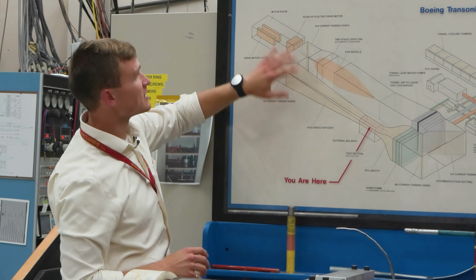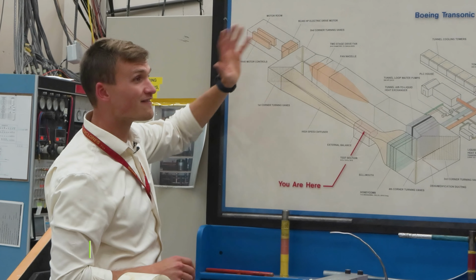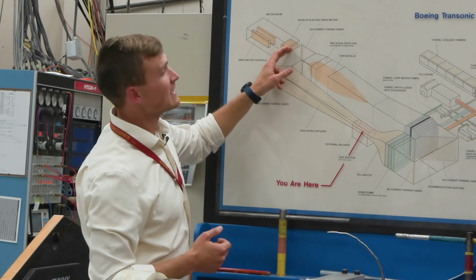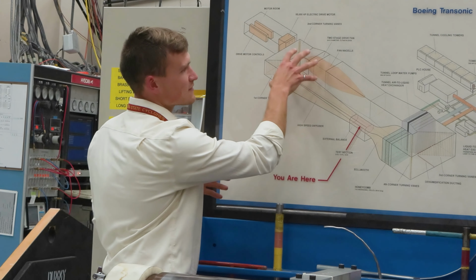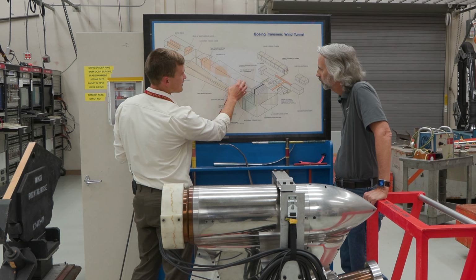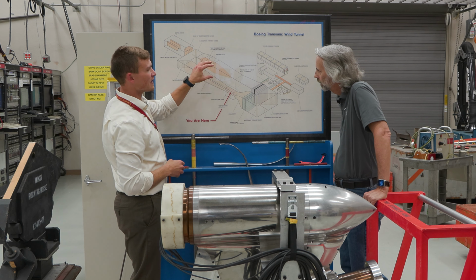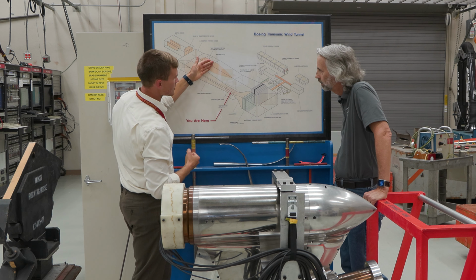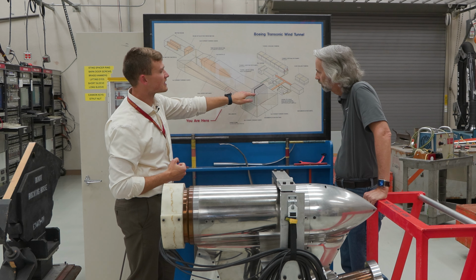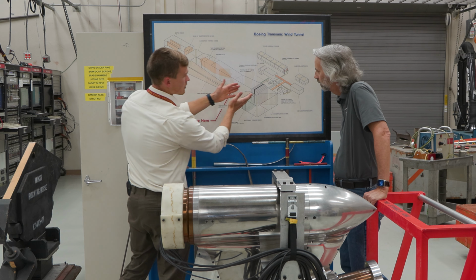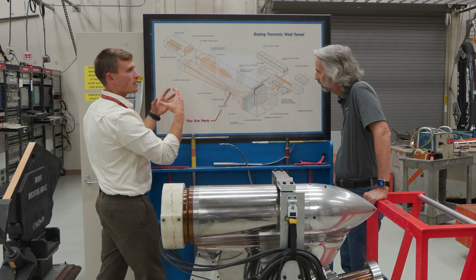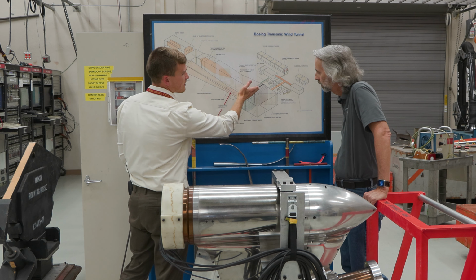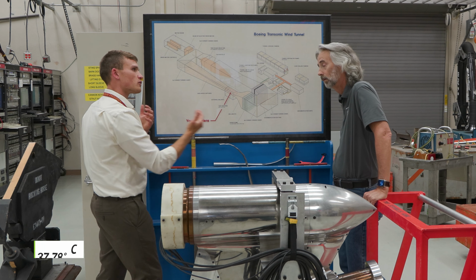And so this fan is being driven by this massive motor, as you can see, 55,000 horsepower. It's like 47 megawatts when it's churning at full tilt. We can't actually walk into this fan section just for protection, but we'll pop out down here and do a quick view of that fan on the downstream side, just after the air is accelerated and has all its energy and pressure. Then we'll walk down and take a peek at the plate fin heat exchanger. There we have all of this air that's been heated up because so much energy has been added to it. We go through that heat exchanger, and on the back side, we're getting to 100 degrees. There's like this 40-degree differential.